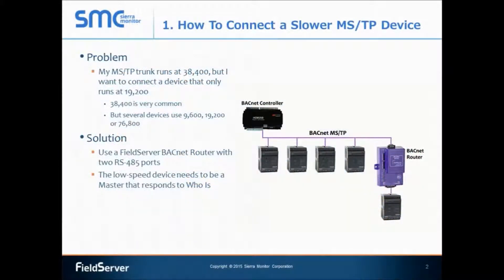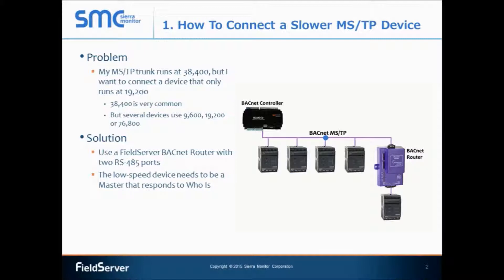Use case number one: how to connect a slower MSTP device. BACnet MSTP has the following baud rates available: 9600, 19200, 38400, and 76800. Even though most BACnet MSTP devices run at 38400 baud, integrators often have to connect devices that run at slower speeds such as 9600 or 19200. As a facilities manager, I have a BACnet MSTP device that does not have the baud rate I want to run my BACnet MSTP network at, and I can't find a substitute product.